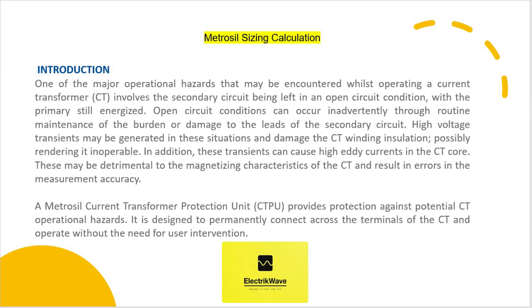In addition, these transients can cause high eddy currents in the CT core. These may be detrimental to the magnetizing characteristics of the CT and result in errors in the measurement accuracy. A Metrosil current transformer protection unit, CTPU, provides protection against potential CT operational hazards. It is designed to permanently connect across the terminals of the CT and operate without the need for user intervention.